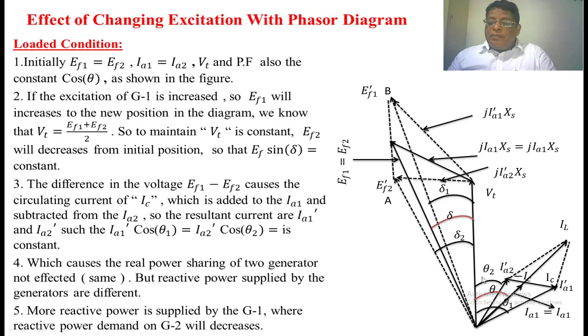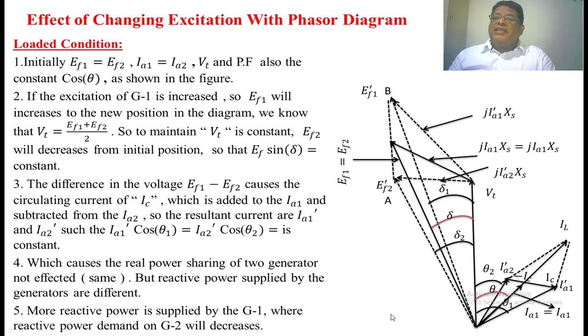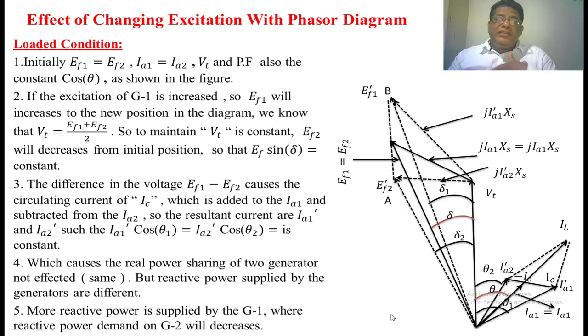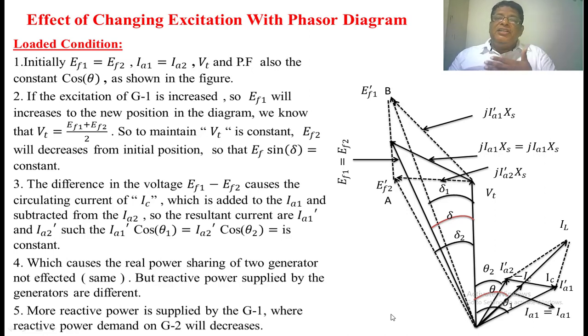The active current supplied by the two generators is constant — that is, the projection of IA1 dash and IA2 dash on the VT phasor is constant. But the vertical component is different — that is, the reactive power supplied by the two generators changes. As the excitation is increased, the reactive power supplied by that generator will be affected, but there is no change in the real power supplied by the parallel operation. So when we increase the excitation of the first alternator, the reactive power supplied by the first alternator will increase, but the real power stays the same. Therefore, the reactive power supplied by the second generator will decrease.